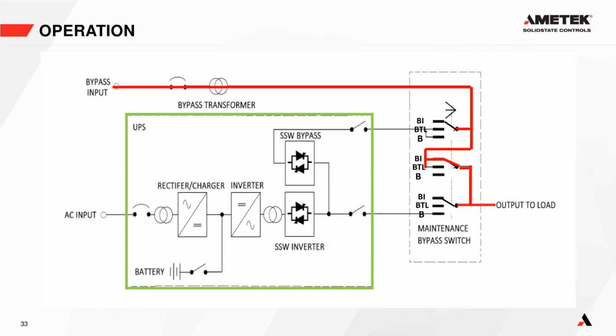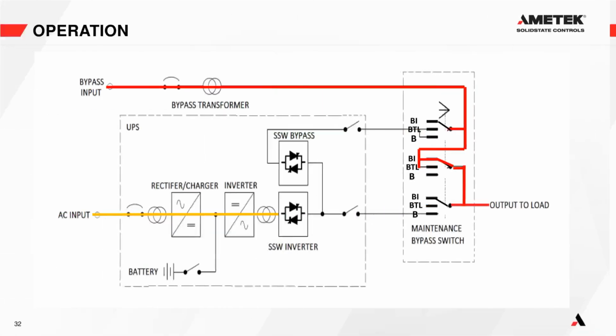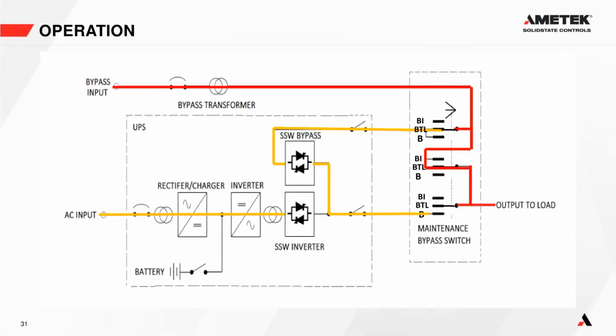Somebody has asked, what's the purpose of having bypass to load? That's a very good question, so let me go over that. Why have the bypass to load position, and why not just have normal and bypass isolate? Going back to the bypass to load position - the reason we have it is we're disconnecting the inverter output from the loads, but we are still connecting the bypass input to the static switch inside the UPS.